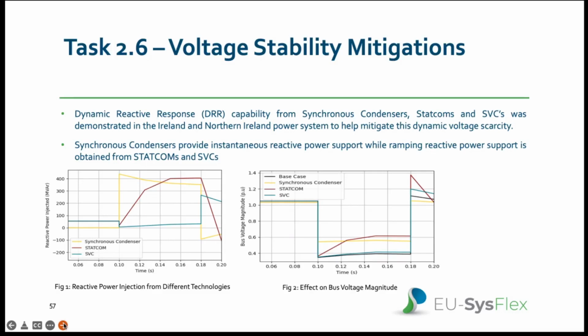Dynamic reactive response capabilities from synchronous condensers, STATCOMs, or SVCs were demonstrated here. As shown in figure 1, synchronous condensers provide instantaneous reactive support, while ramping reactive support is obtained from STATCOMs and SVCs. Our results show that synchronous condensers and STATCOMs are the most suitable technologies capable of providing this dynamic reactive response service for mitigating this scarcity.